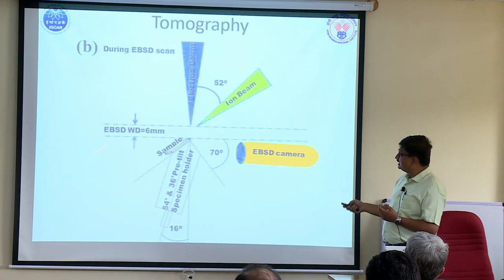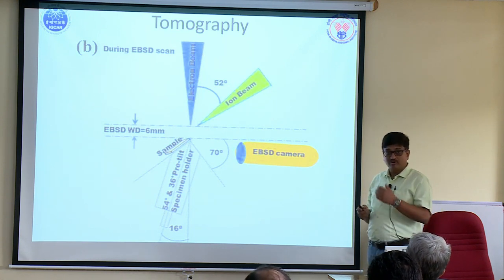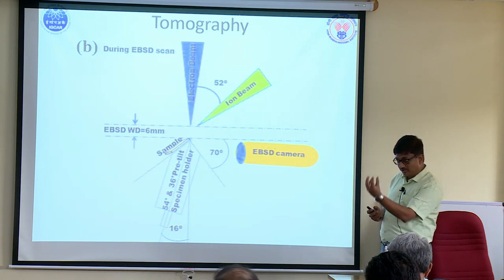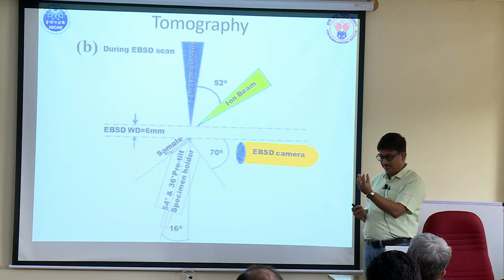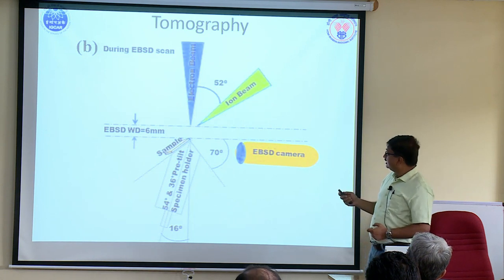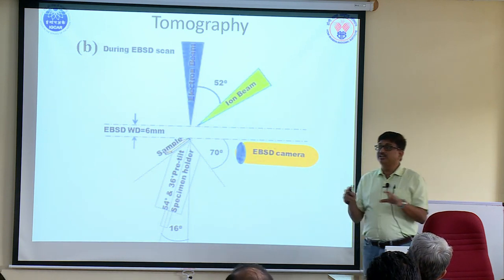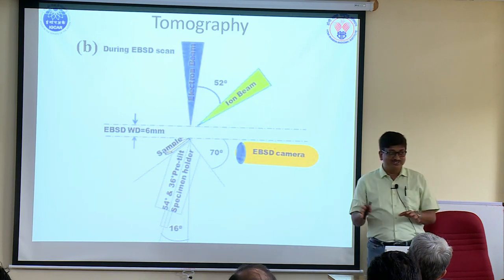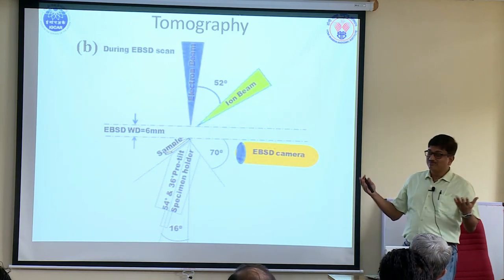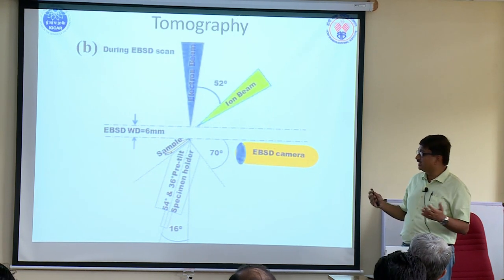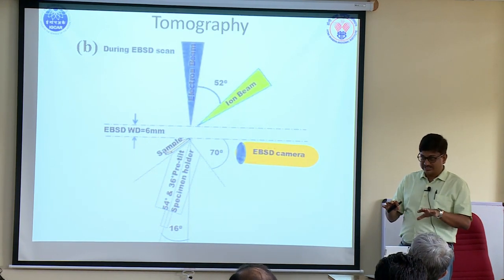So as you can see here, we have gone to 6 mm. We have gone down, so we have basically rotated 180 degrees, gone down by 2 millimeters, 1.9 millimeters, yeah. And once you define that, you start doing the EBSD. This is an automated process, by the way, you don't do it manually, it's impossible, because you will be doing hundreds of slices or some 300 slices, you can't do that manually. So everything is to be set up there.